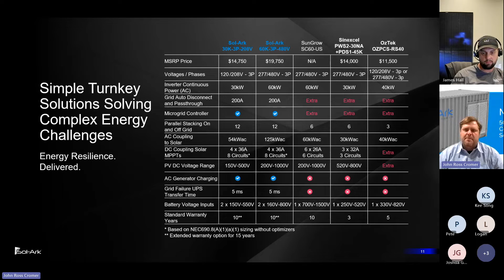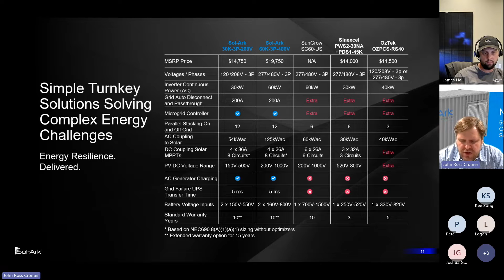Sometimes residential installers get surprised by that, because they're used to having time-of-day settings or demand management settings included in the feature set of the inverters. But now in most cases, you're utilizing inverters that really weren't developed for all these solar-oriented features, and they come back to haunt you with all sorts of commissioning difficulties. So it's very easy to get these projects installed and functional. There's a lot less gotchas with the Sol-ark equipment.